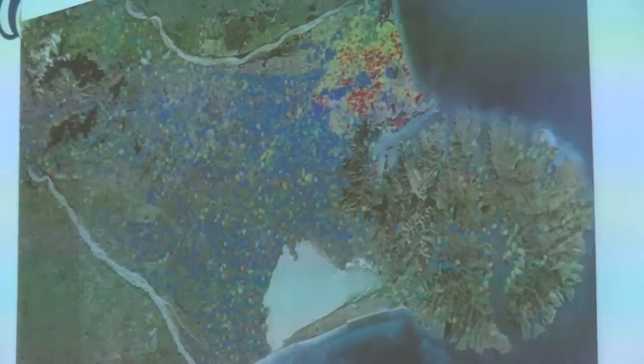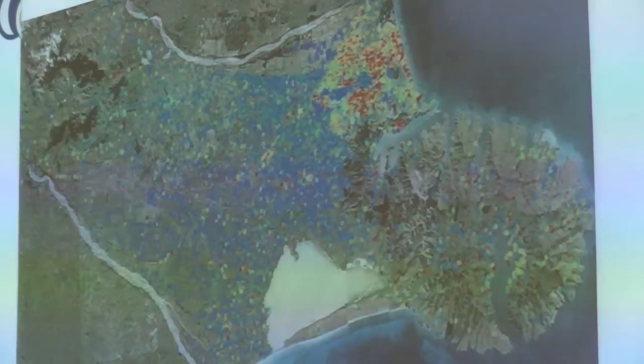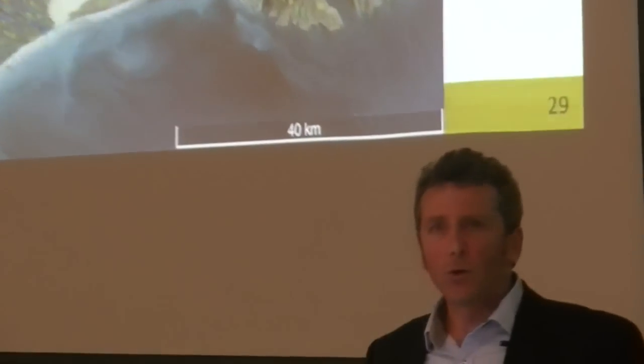The areas in blue are not such an issue. We can actually turn this into a concept we call hosting capacity — the ability of each home in a network to host solar power, in other words how many kilowatts of solar power that home can inject into the grid before it could give rise to power quality issues. That is something we've developed at the epicentre and are providing to distribution companies to help them understand their networks' ability to host solar power.